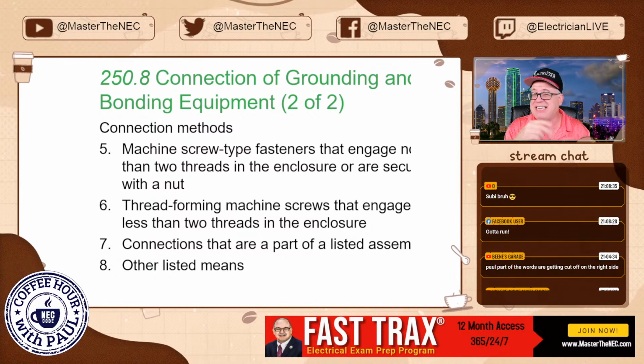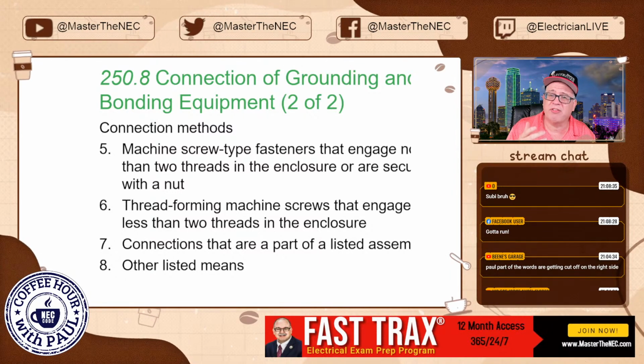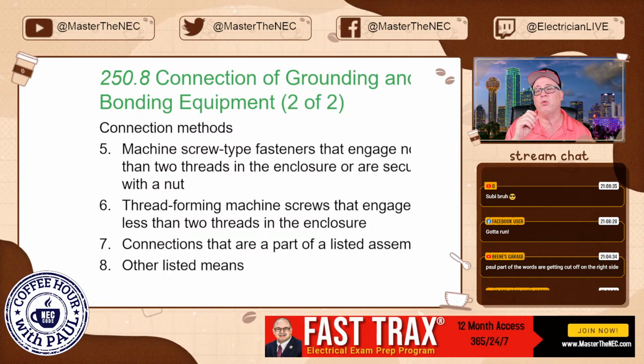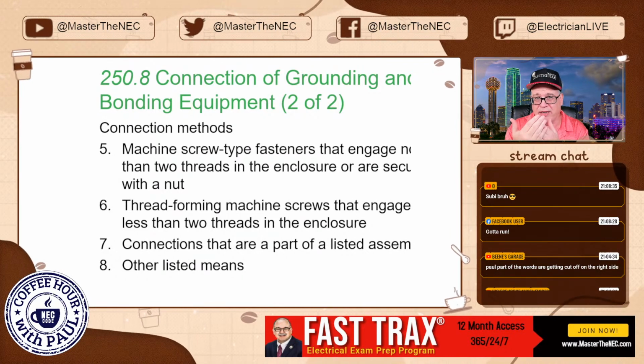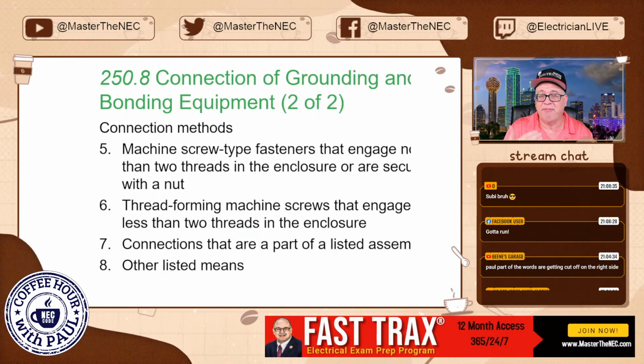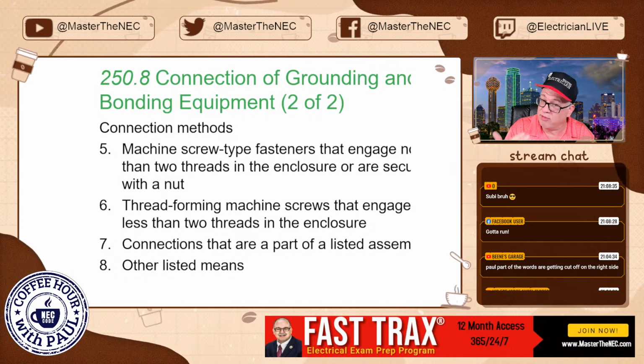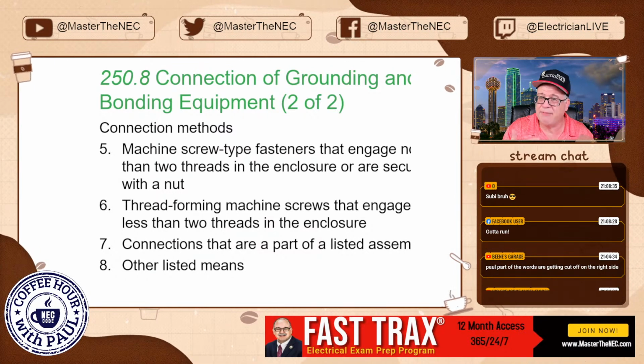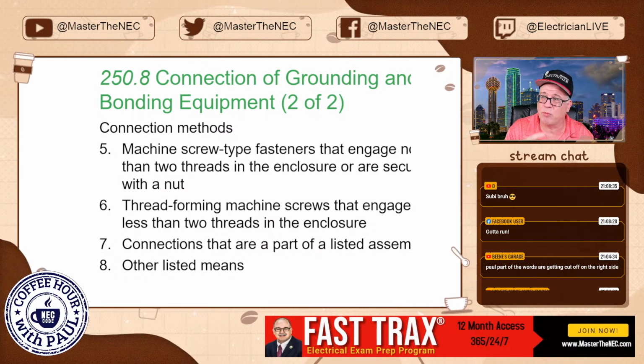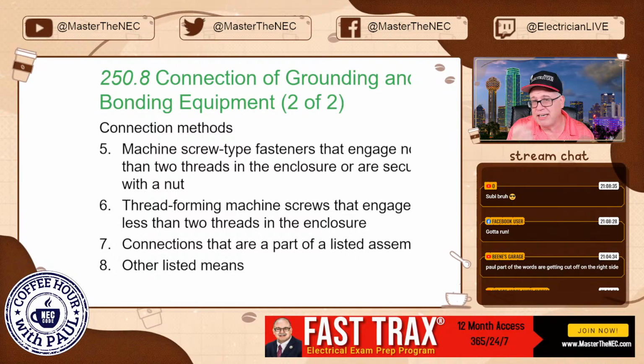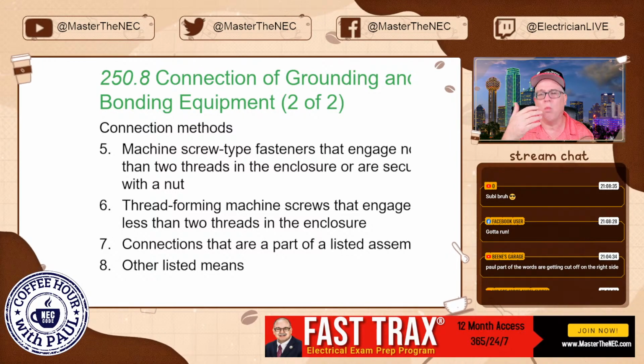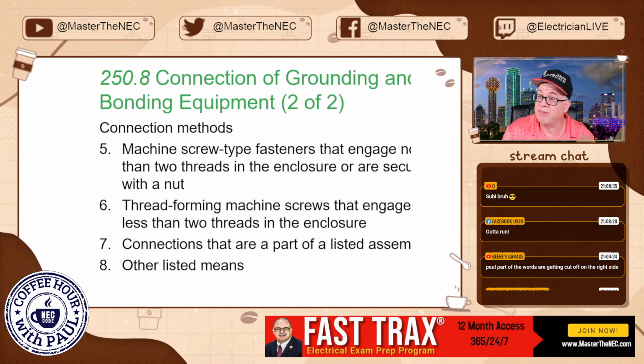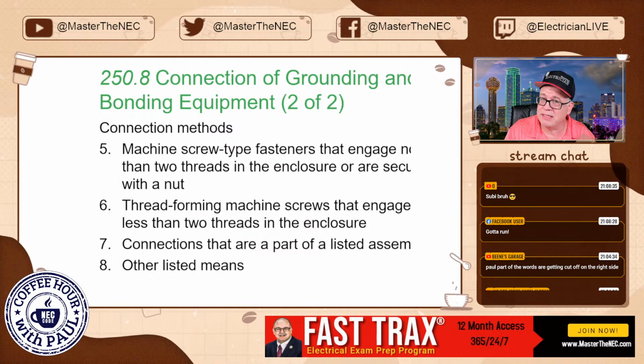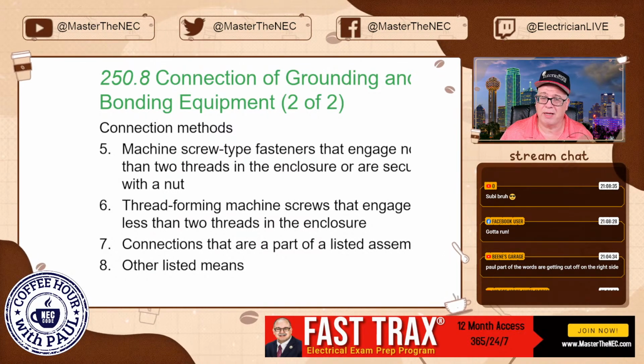But again, if it didn't, then you could still use a machine screw, but you're going to end up having to do what? You're going to have to put a nut on the other end to make up for the fact that you don't have the 2 threads. Even though you're using a machine screw, if you're not going to engage 2 full threads, which most of the cabinets that have that green screw or ground screw will give you, right? But if not, you can still do it. Just you better put a nut on it, okay?